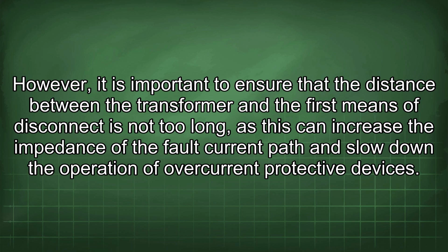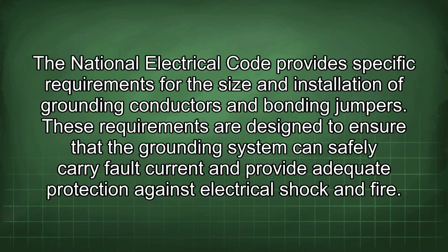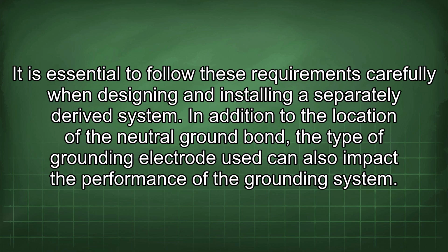However, it is important to ensure that the distance between the transformer and the first means of disconnect is not too long, as this can increase the impedance of the fault current path and slow down the operation of overcurrent protective devices. The National Electrical Code provides specific requirements for the size and installation of grounding conductors and bonding jumpers. These requirements are designed to ensure that the grounding system can safely carry fault current and provide adequate protection against electrical shock and fire. It is essential to follow these requirements carefully when designing and installing a separately derived system.